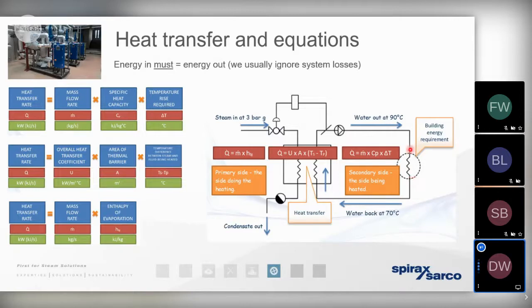Well, we can calculate the energy requirement. That's typically referred to as the Q value, by multiplying the mass flow rate of the process by the specific heat capacity by the temperature rise. Well, the mass flow rate requirement, we can simply get that from the client or from the process owner. They will help us to understand how much media needs to take on that temperature.